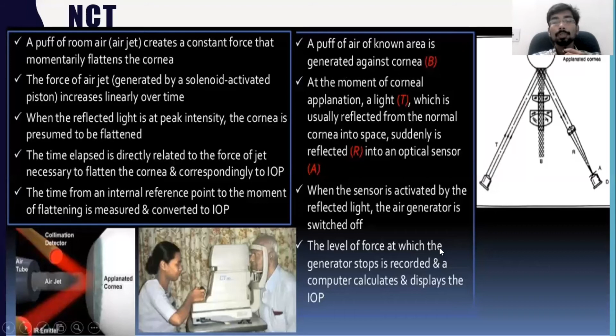A puff of air of known area is generated against the cornea, B, and at the moment of corneal applanation, a light T, which is usually reflected from the normal cornea into the space, suddenly is reflected, R, into the optical sensor A. When the sensor is activated by the reflected light, the air generator is switched off. The level of force at which the generator stops is recorded and a computer calculates and displays the IOP.